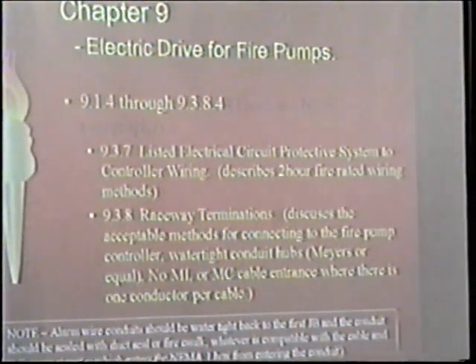Listed circuit protective system, and it's something you're probably not familiar with, but MI cable was an electrical protective system. There are a couple of others out now that go into standard conduit. So you should be aware, on any retrofit, any conduits coming through a building need to be run in a 2-hour wire or a 2-hour protective system, or they need to be encased in 2 inches of concrete.